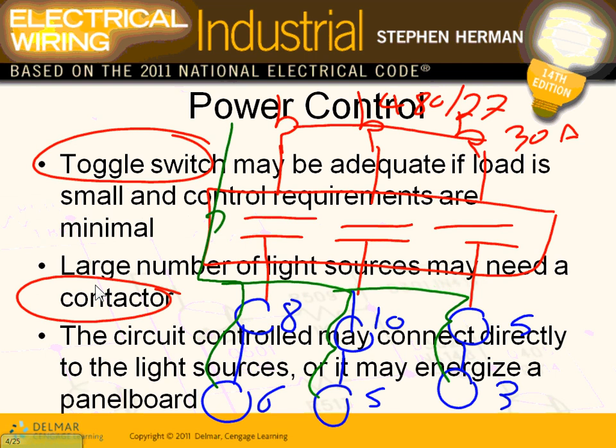How do you control this magnetic contactor? Through the coil — I can interface this coil from a laptop, push a button on the laptop. This will be your control system. I can make a clock control this contactor, a timer, anything you want to interface with this contactor. They call them lighting contactors and use them a lot in major parking lots. They can be three-pole, four-pole — they can make multiple-pole contactors.